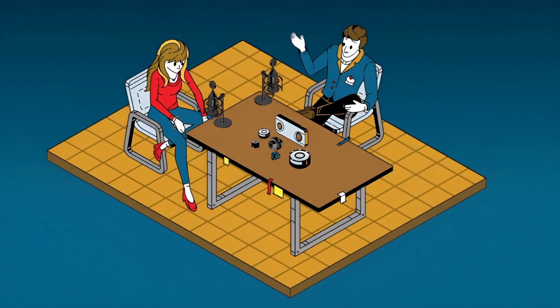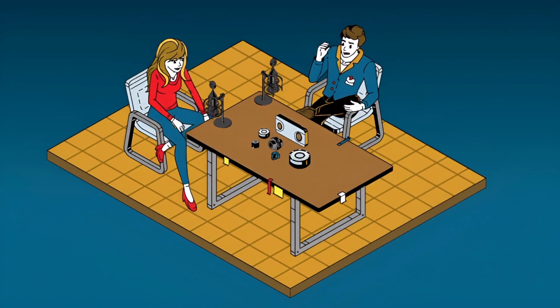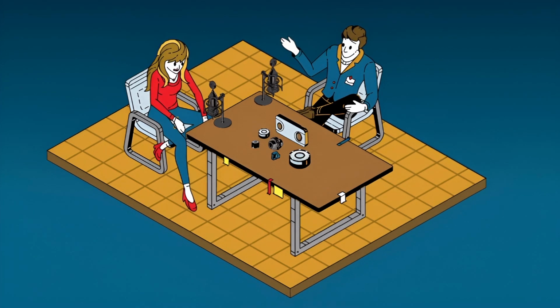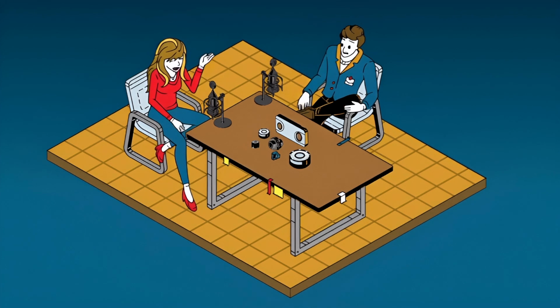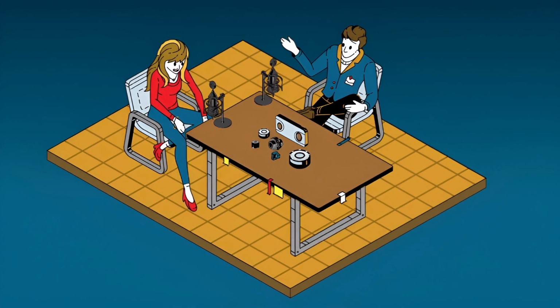Which I guess ties into the next point, preventing problems before they happen. You got it. Third is minimizing downtime. This is really about being proactive instead of reactive. Exactly. If you stick to a regular calibration schedule, you're much more likely to catch potential issues, little drifts or inconsistencies, before they become total failures. So you avoid that sudden everything-grinds-to-a-halt moment. Fewer unexpected stops in production, fewer delays in testing. It avoids those really costly interruptions. Okay, that ounce of prevention idea makes total sense.